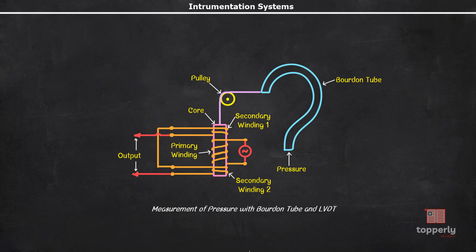But the output of it is displacement. That is, when pressure is applied, the tip of the Bourdon tube gets displaced by some amount. However, this displacement cannot be fed to a digital instrument. So what we do is, using a pulley and string system, we transfer this displacement to the core of an LVDT.